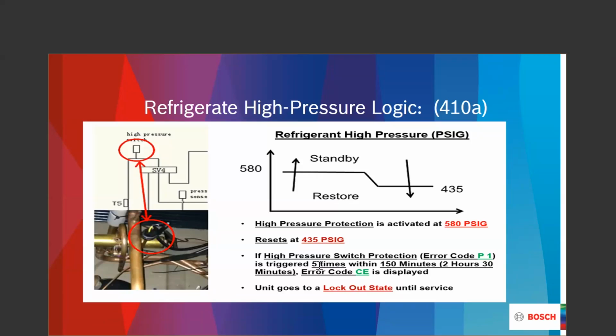Okay. Of course, you've got to look at the dirty coil. Then you may look at restrictions in the refrigerant line. There's a lot of things that are problematic with head pressure in an air conditioner. Then my system goes into the heat pump mode. Now that outdoor unit is the evaporator and the indoor unit is the condenser. Now I have all of those things on the inside that are problematic with head pressure.